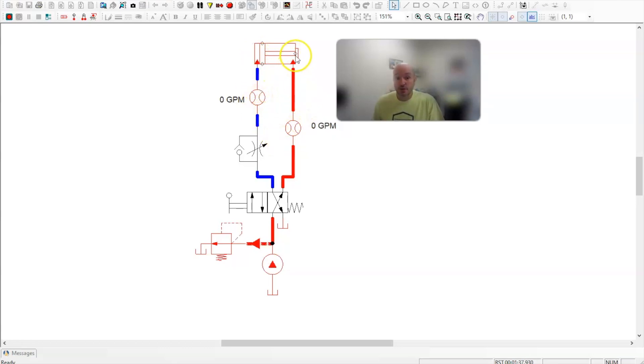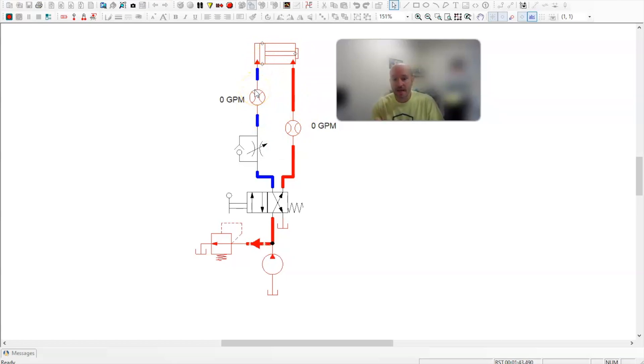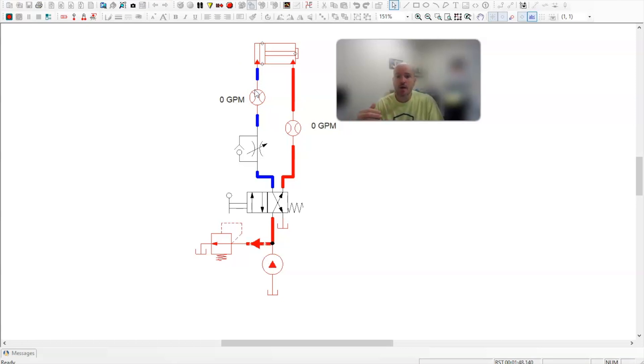Now when it's retracting, the oil is coming out the A port. So that's really important. You always have to ask yourself, what is my port doing when it is extending and when it is retracting, when you're trying to diagnose how a meter circuit works when it comes to hydraulics. Because this is confusing.